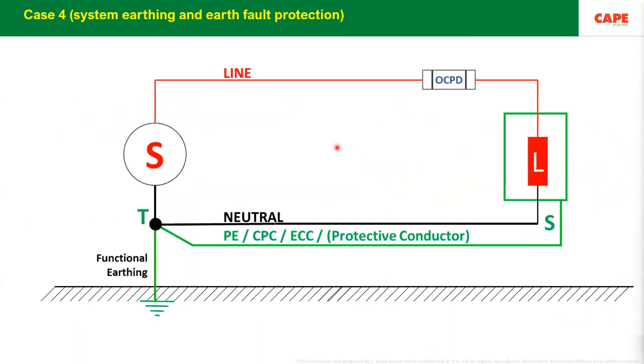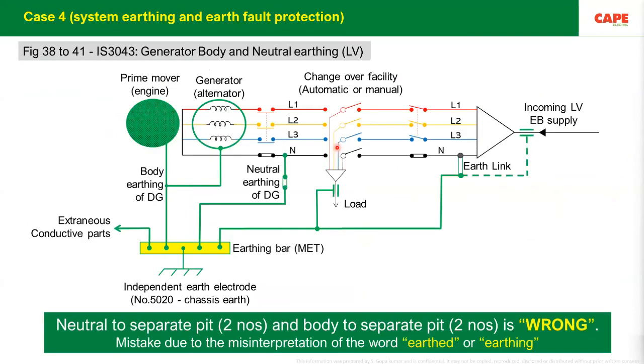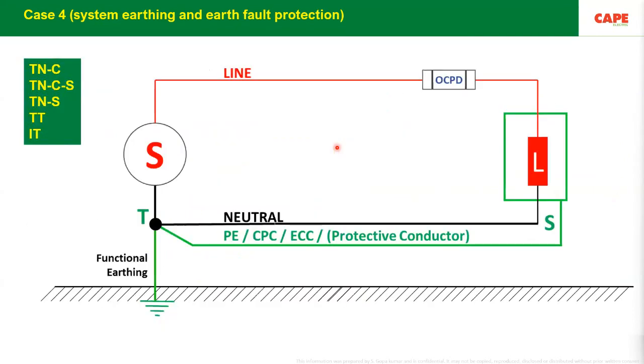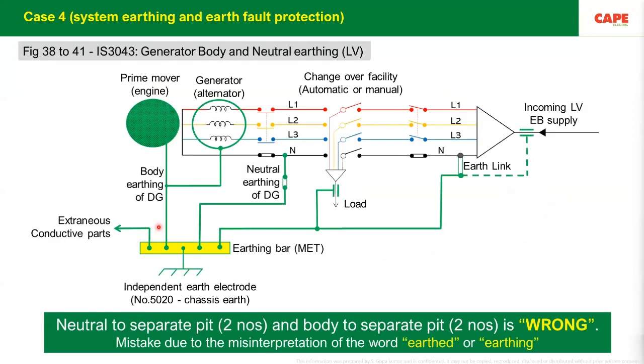Very, very important. Number 4, earth fault protection. What is earth fault protection? Now I am showing you a TNS network. You have a source, you have an OCPD, which stands for MCB, and you have a load. The green is nothing but the body of the equipment, and then you have a protective conductor connected back to the neutral of the source. You can find this kind of picture in all the IS standards. The IS standard I am showing you is IS 3043.